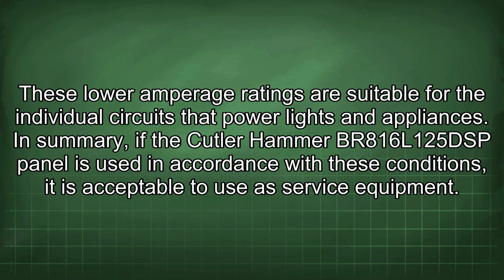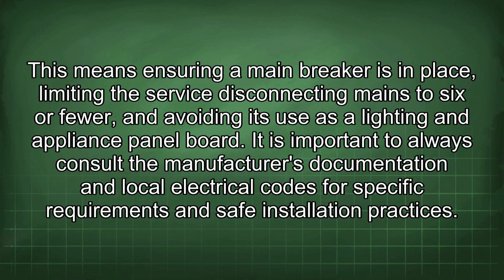In summary, if the Cutler Hammer BR816L125DSP panel is used in accordance with these conditions, it is acceptable to use as service equipment. This means ensuring a main breaker is in place, limiting the service disconnecting mains to 6 or fewer, and avoiding its use as a lighting and appliance panel board.